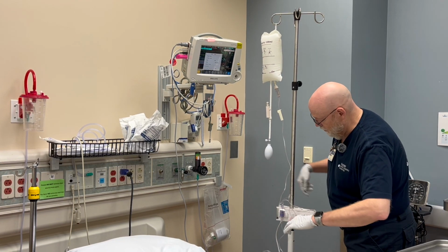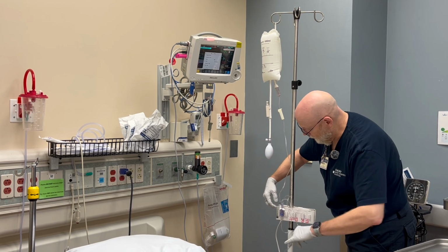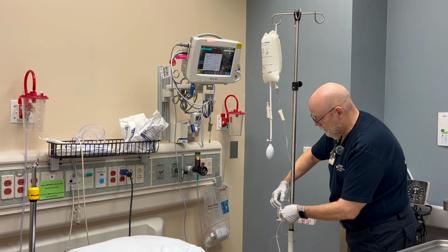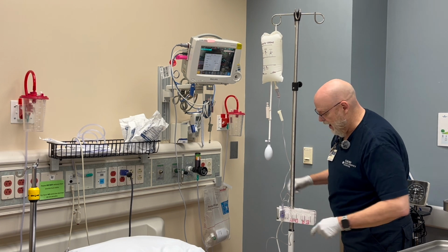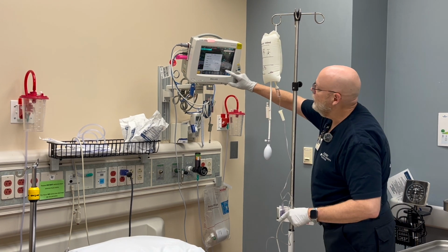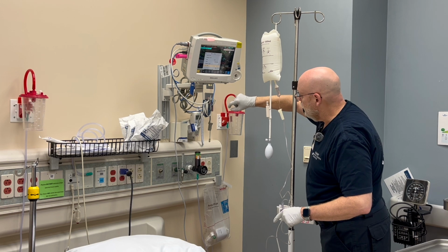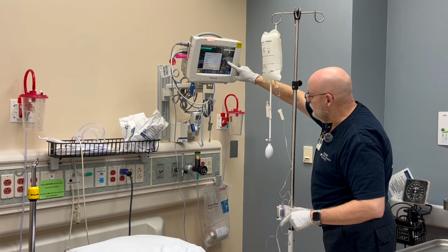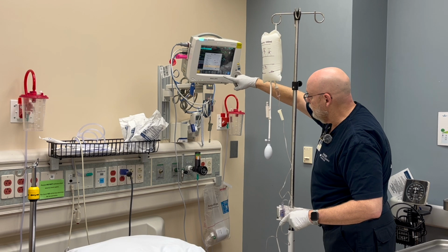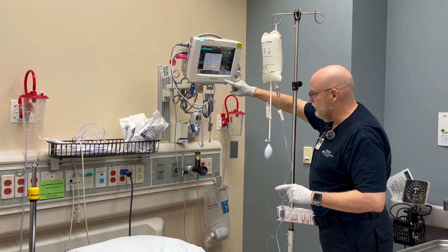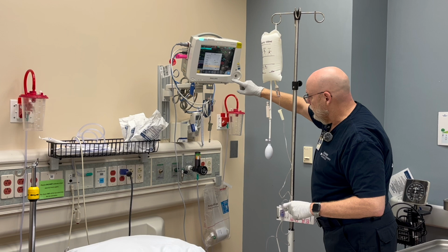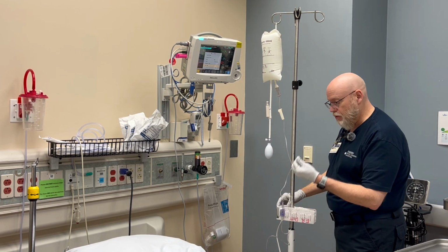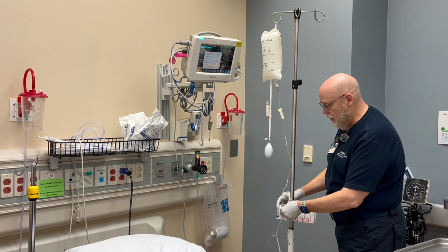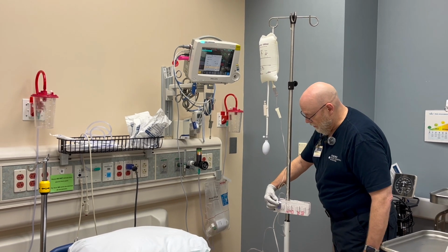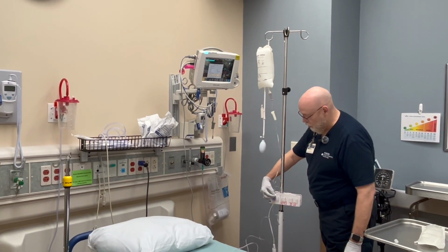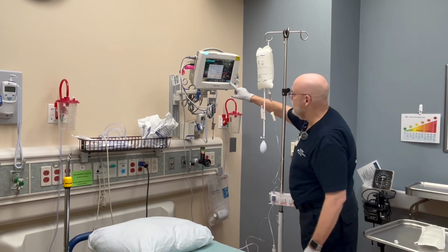This is the patient end, so I'm going to turn it off to the patient. I'm going to remove the cap. And then you can flush a little bit if there's a little bit of air. Now it's at atmospheric pressure. I'm then going to touch 0 ABP. It'll beep once, it'll give me a 0 in that parameter, in parentheses, and it'll beep a second time. Once it beeps the second time, you have then zeroed it. You can place a new or a clean stopcock or a clean cap on the stopcock. Turn the stopcock back to off at the port onto the patient, and you should be getting a reading in your parameters.